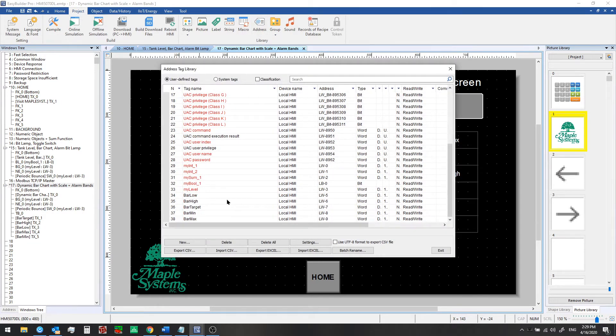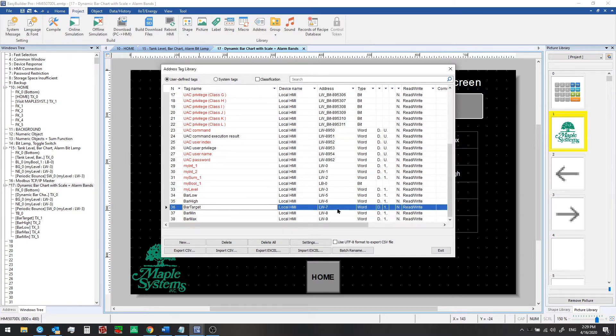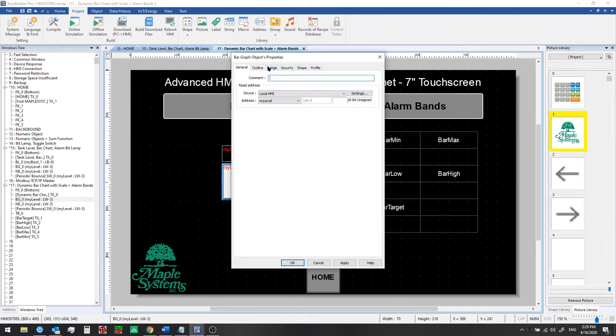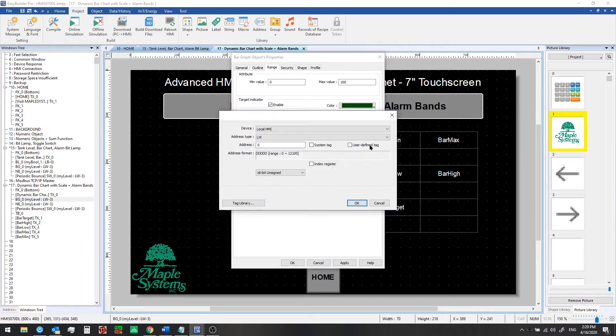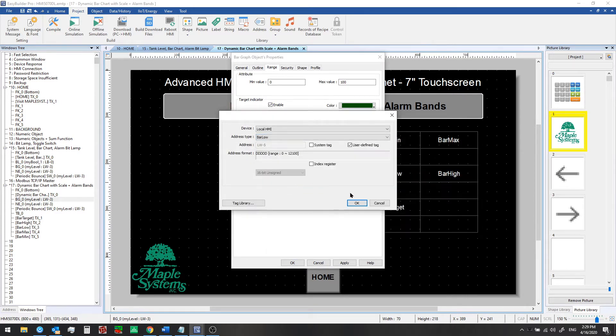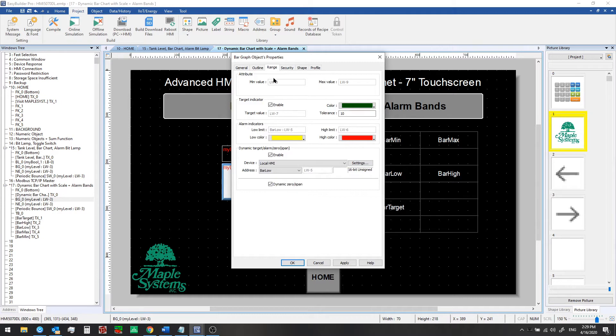So we'll start from bar low at local word 5 and we'll go to target at local word 7, and then min and max at local words 8 and 9. We'll use those addresses in this example. Now we'll check this box and set the first tag bar low, and then we'll check dynamic 0 span and it will automatically pick the set of consecutive registers following that, and that will match up with our user-defined tags we've set up.